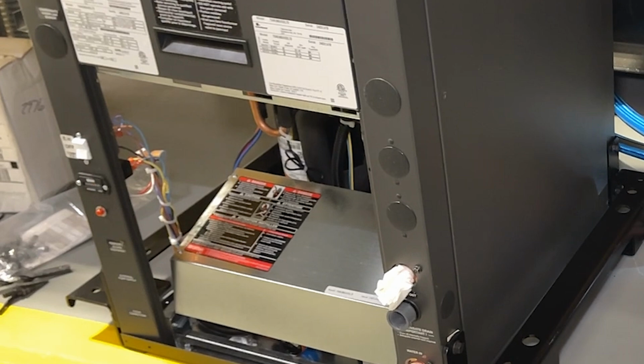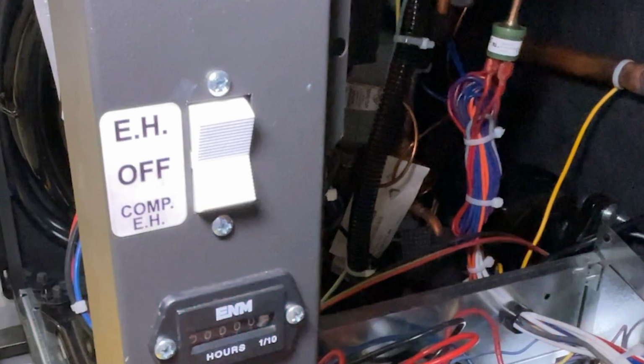The unit exterior has multiple 3/4 inch knockout locations for incoming electrical connections. Select the appropriate knockout relative to delivery of electrical service in the room or enclosure. See electrical schematics located in the operation manual for connection location. Once electrical service has been installed, turn on power to the HE by switching the power toggle to the bottom position.